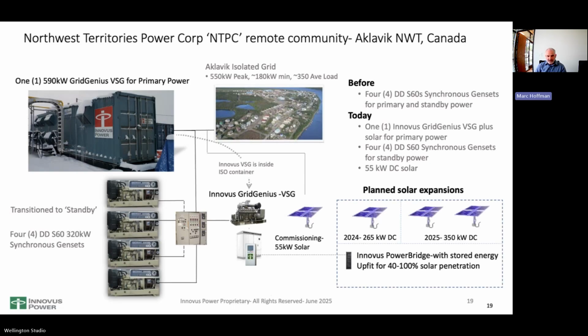In this case, we replaced 4 Detroit Diesel S60 gensets that had been there. When I say replaced them, they went into reserve and weren't used in any 24-hour cycle. The only time they were used, staying in the powerhouse, was when the VSG was being serviced. So essentially, one VSG at 600 kilowatts replaced four Detroit diesels that were operating in that community.